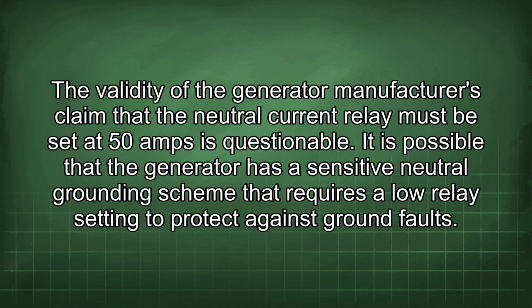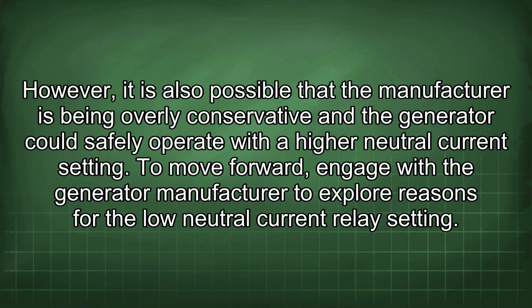The validity of the generator manufacturer's claim that the neutral current relay must be set at 50 amps is questionable. It is possible that the generator has a sensitive neutral grounding scheme that requires a low relay setting to protect against ground faults. However, it is also possible that the manufacturer is being overly conservative and the generator could safely operate with a higher neutral current setting.